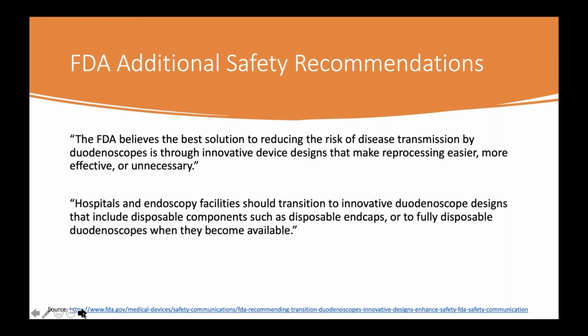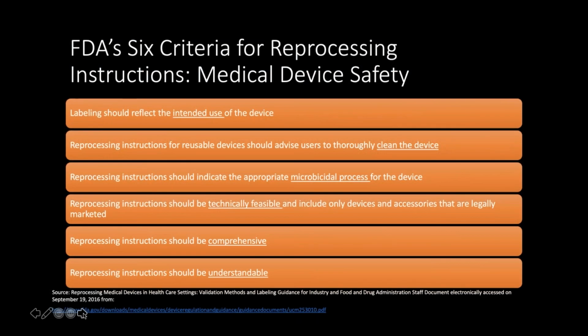And what I really liked about this comment was it gave facilities a stepwise approach based on where they were in their current journey. So for example, if they were using 10-year-old devices that had never been serviced and they had issues with their HLD, with their AER, then that's where they need to start. Versus facilities that may already be doing a great job with HLD, what is that next level? Is that a disposable device? Is that sterility? Is it monitoring of the process? And so, they talked about rendering the reprocessing device unnecessary, if you will, right? And so again, this is an example of how we can make that transition.